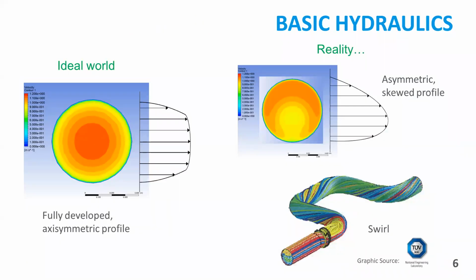So you saw on the list there something about hydraulic disturbances, and that's going to be something that we're going to come back to on a few occasions in this paper. It's very important. Hydraulics is the flow of the water through the pipe and how that behaves. And meters, when they're manufactured, the manufacturers will put them on their test rigs to make sure they work properly before they deliver them to us.